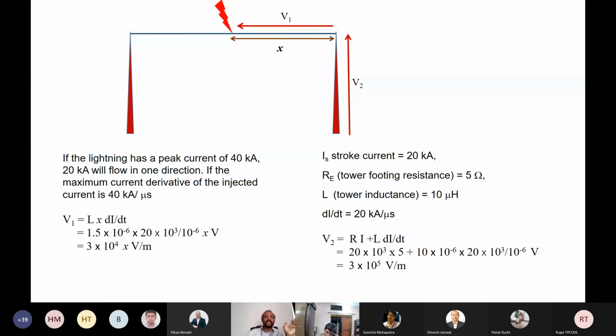Now, if the maximum current derivative of the injected current is 40 kiloamperes per microsecond, I am sure that you all know this equation. When you put that in, we get something like 30 kilovolts per meter. Okay, and then if you consider the tower to have a certain impedance, then when the current flows through the tower, there will be another voltage generated.